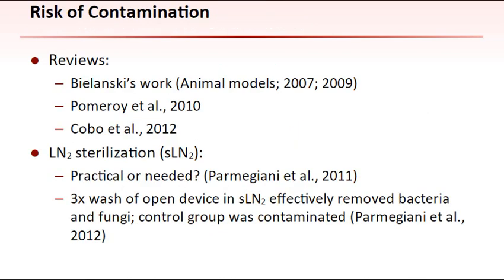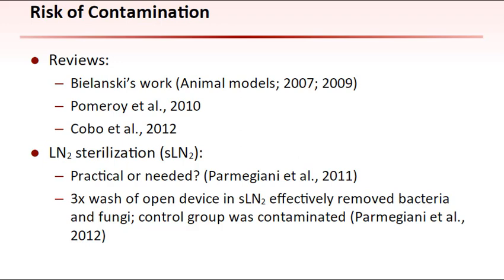The risk of contamination to culture medium or gametes and embryos under clinical conditions is remote. However, it has been shown to be a real risk. This risk could be eliminated by pre-warming and serial rinsing of the open device in ultraviolet sterilized liquid nitrogen. Considering the FDA's current good manufacturing practice regulations mandate that vitrification devices be effectively sealed, it seems logical that similar storage requirements may one day be instituted, especially once randomized controlled trials demonstrate their competency.